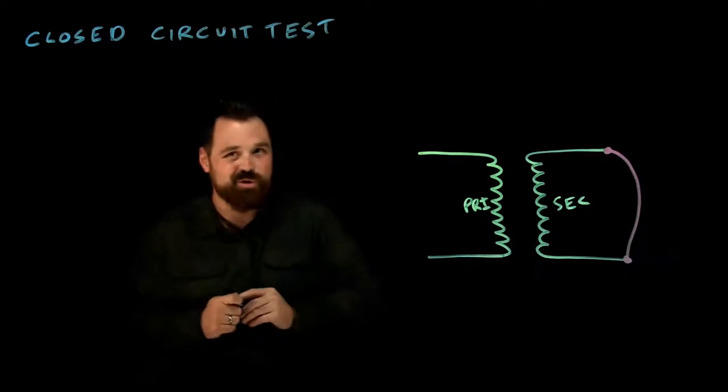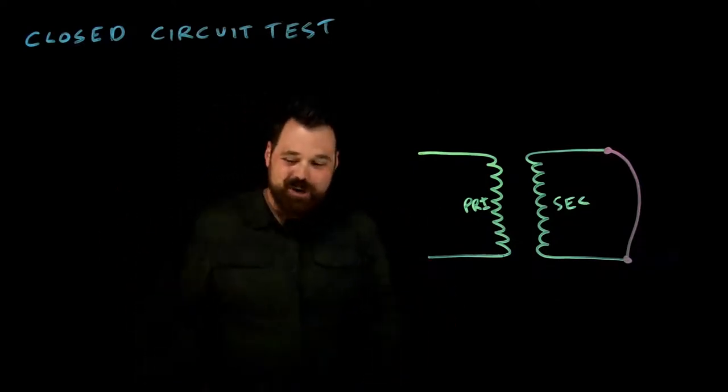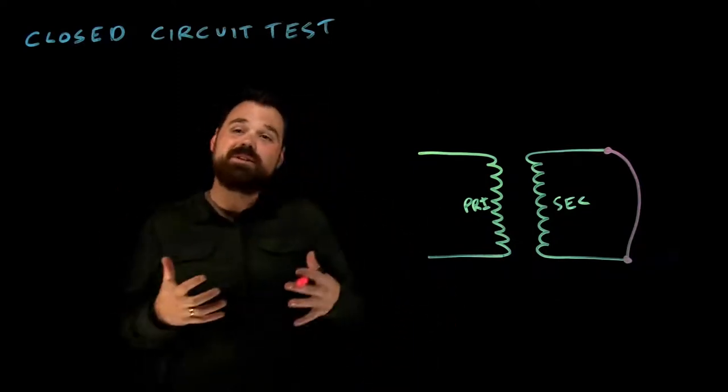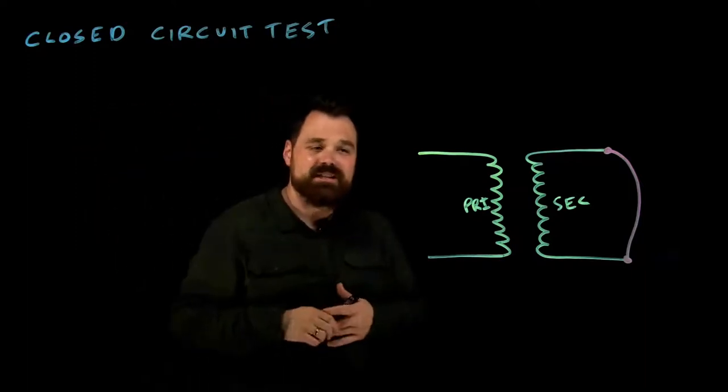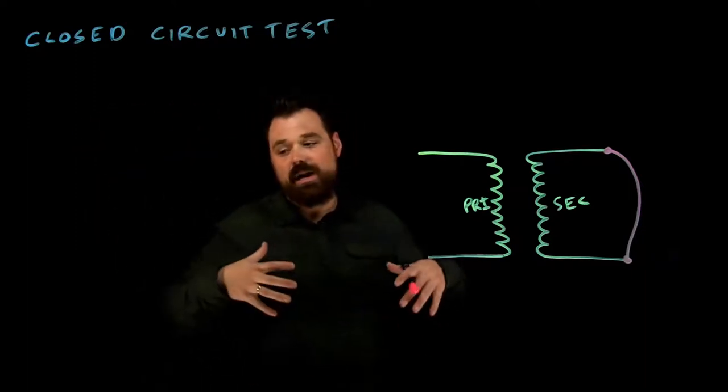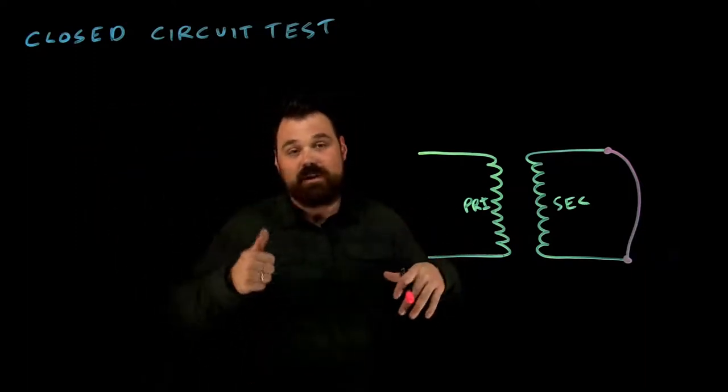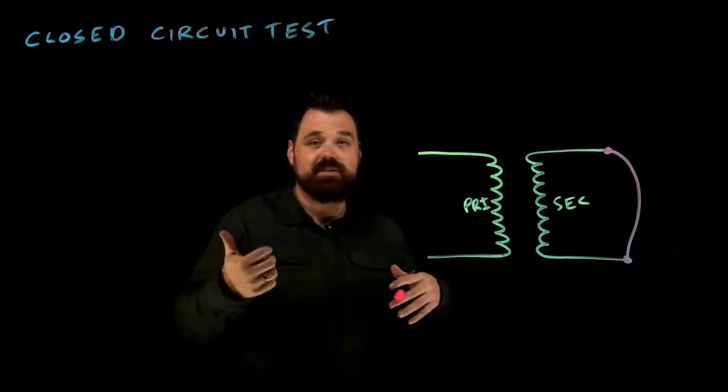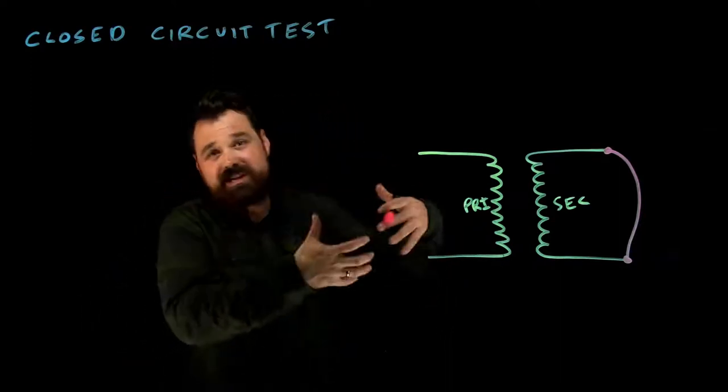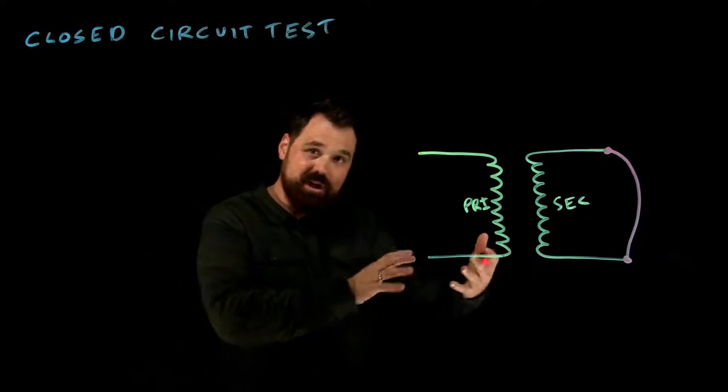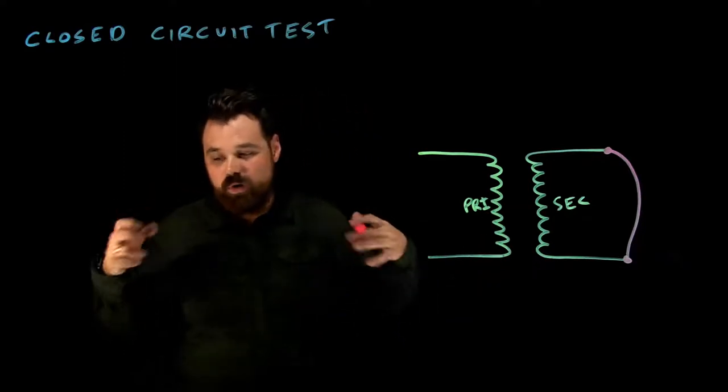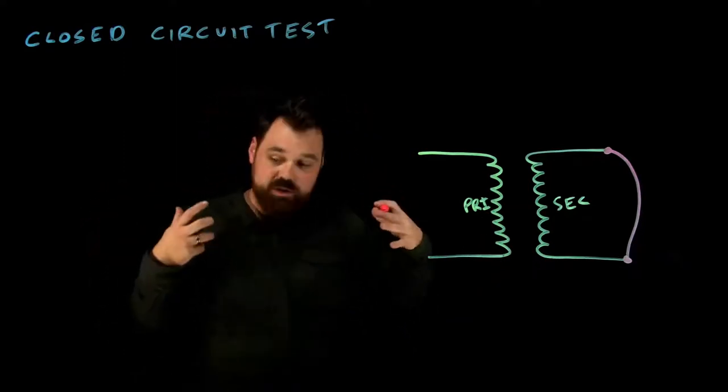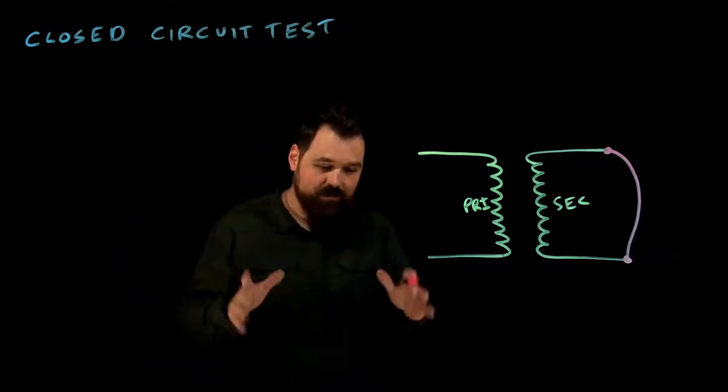What we're going to do is short it out. Now let's talk about it. With this closed circuit test, we're using it to find two things: the percent IZ of the transformer, or the percent voltage impedance required to overcome the losses of the transformer, or we can even use it for copper losses. And that's what our wattmeter will measure.